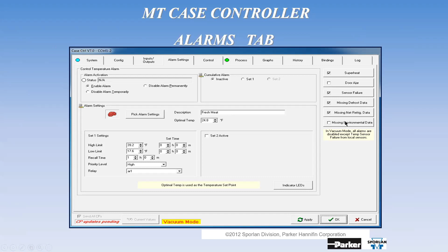Why would I have this? Let's just say somebody is doing something on the HVAC system and they disconnect the node that's taking the temperature and relative humidity for the store, and my case controller is looking for that as an input, and suddenly that input disappears, okay, it's going to get an alarm.